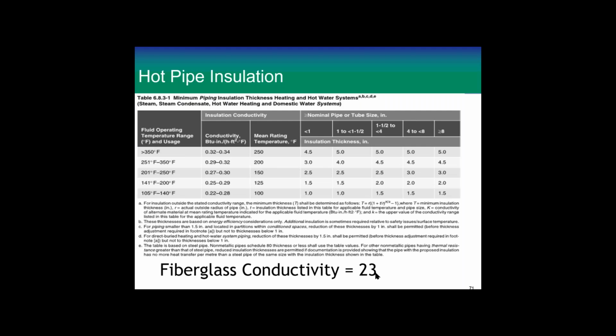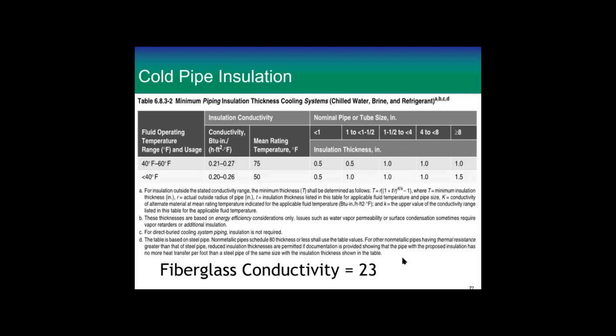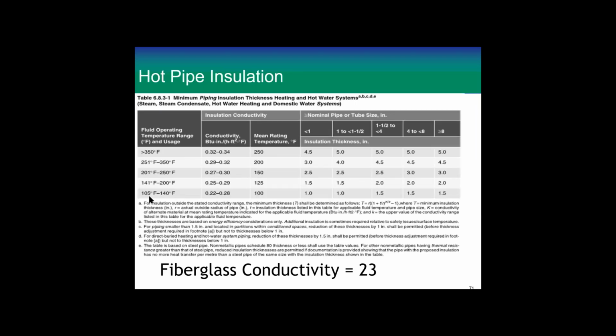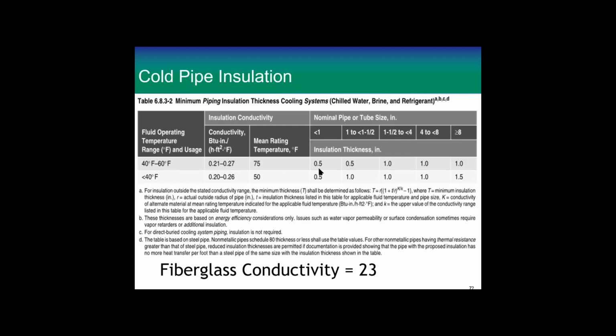Fiberglass conductivity of 23 is kind of the center of what we've been using here. And if it is not 23, then you have to use this equation, which has an exponent in it. So I'm just warning you that the thickness of the insulation grows very quickly if you have conductivity that's worse than fiberglass. And this is the cold pipe insulation. You'll notice that we don't require insulation on cold pipe warmer than 60 degrees, which means that if you've got pipe between 105 or less than 105, but more than 60, as far as the energy code requires, you don't have to insulate it. Now, this might not be a good idea in your building because that pipe could sweat.